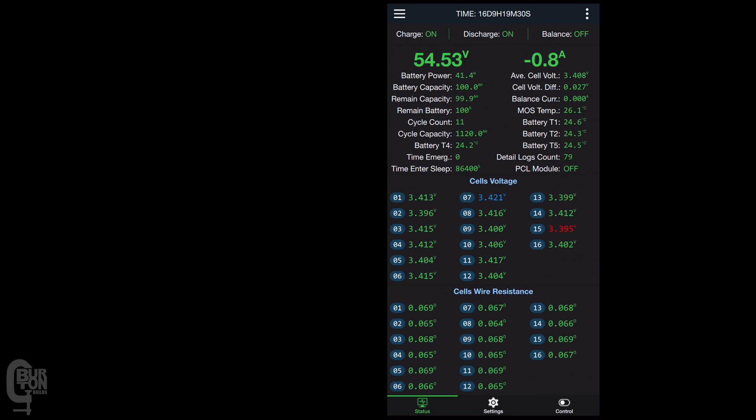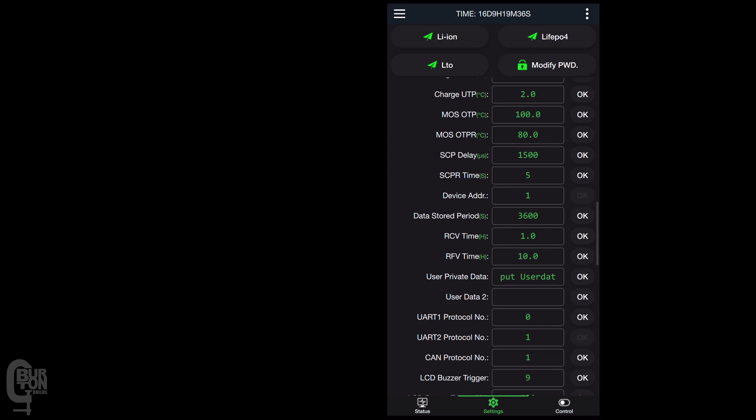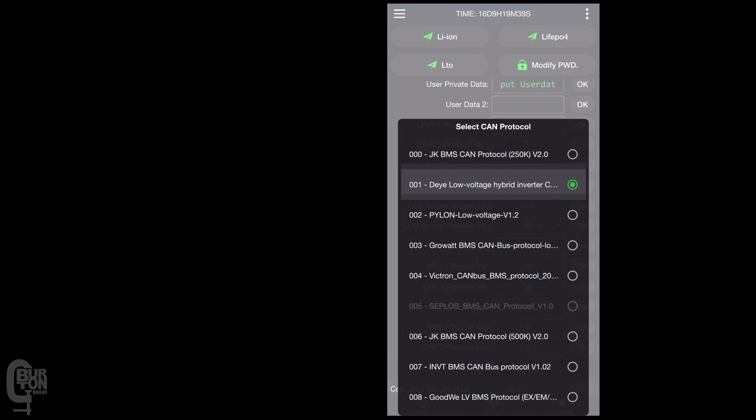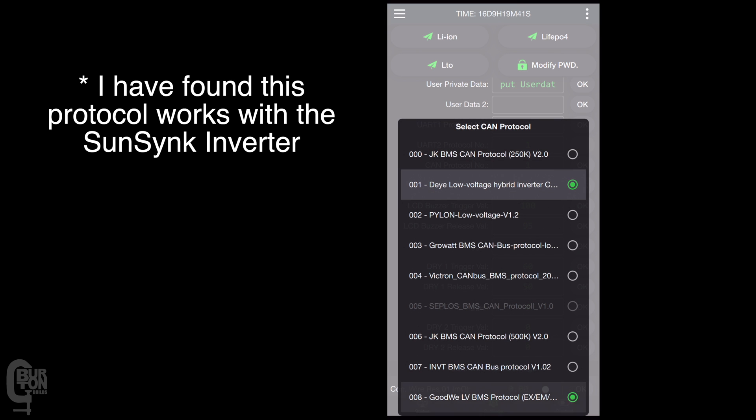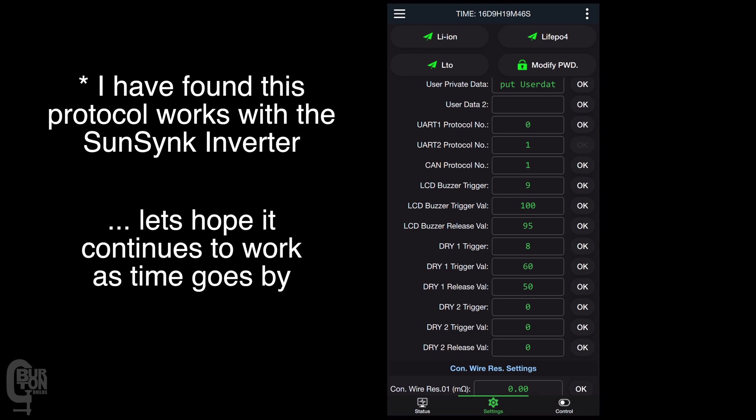The first thing you need to do is select the appropriate CAN protocol for your inverter. To do this, just open up the JK BMS app and then head over to settings. Then scroll down to CAN protocol number and select 001 Deye low voltage hybrid inverter — however you want to say that, and then click OK to save the setting to the BMS.